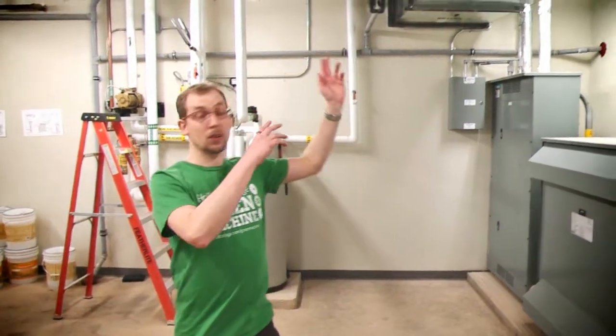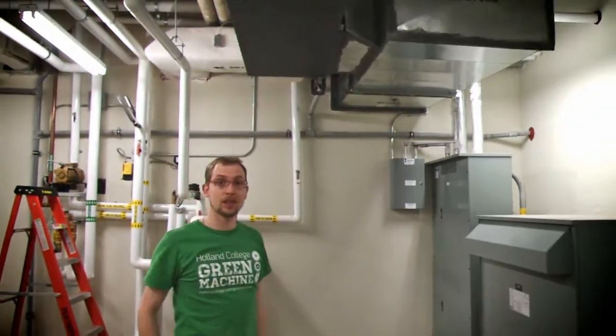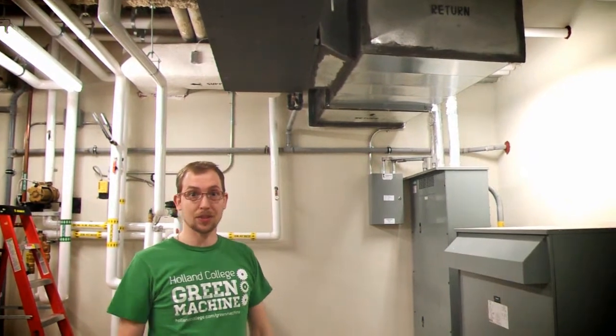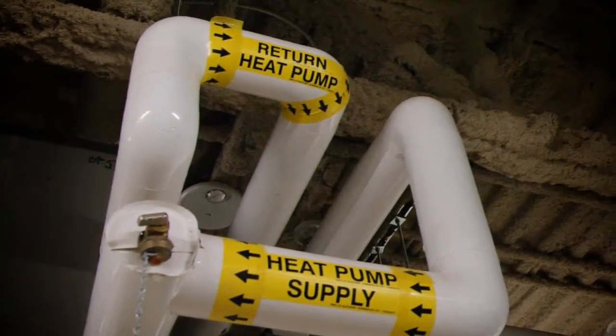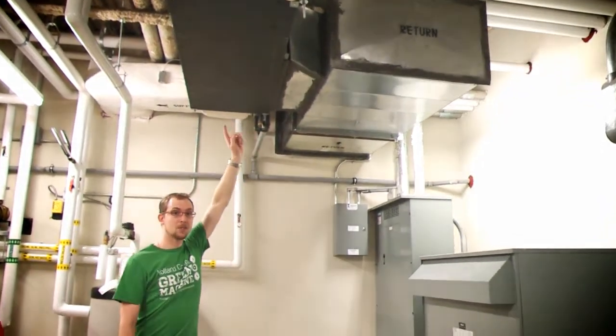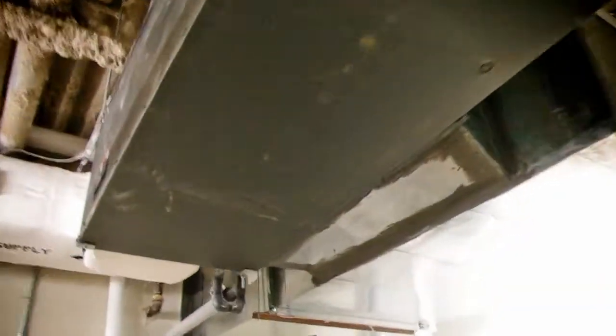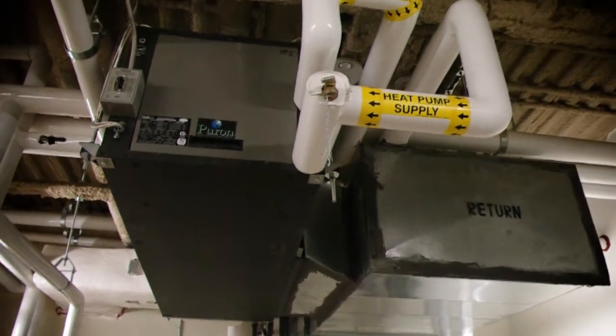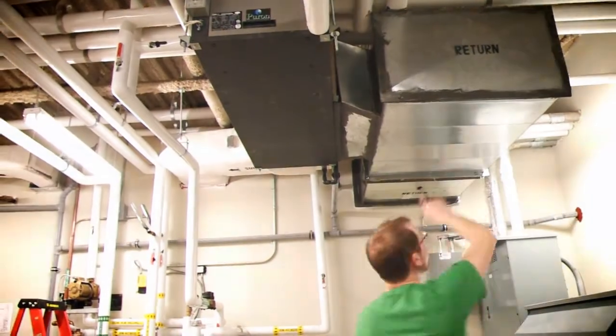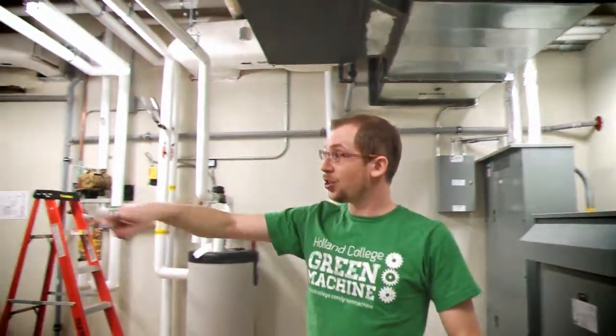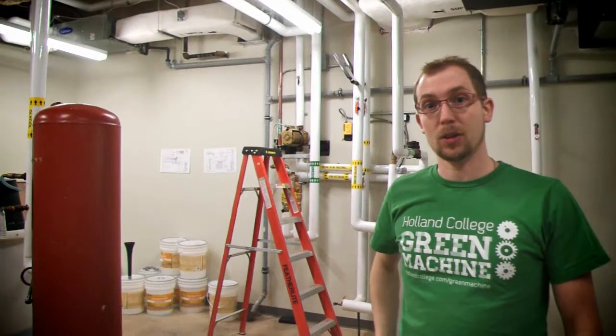So above me is one of the many heat pumps that the geothermal system supplies to. You can see here we have the supply line and the return line. If you follow the supply line, it's going to go into the heat pump system, and from there, whatever heat was collected, it's going to be pushed through in what we call a forced air system. That's going to supply the building with heat. Anything excess is going to come back out through the return, and that's going to continue on back to the top header that you saw at the very beginning of the video.